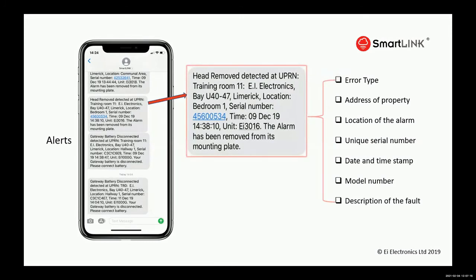So this is a message that you get on your phone if you have one, text or email messages. So you get the error type or whatever has happened, the address of the property, the location of the property itself, the unique serial number of that device, the date and timestamp that the event has happened, the model number that has given the activation, and the description of the fault. So if you just look there, it's head removed, detected at UPRN, which is the training room 11 in Ei Electronics. The serial number was such a number. It's on the 9th of December 2019 at 14:38. The unit is a 3016, and it's been removed off its mounting bit. So that's the level of detail that goes into the message that you do get.